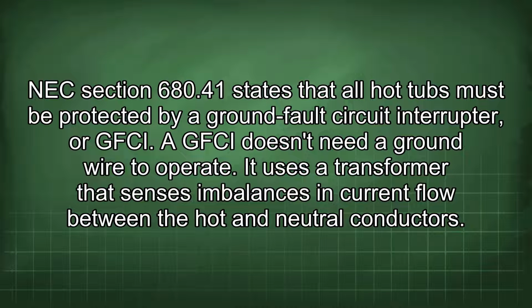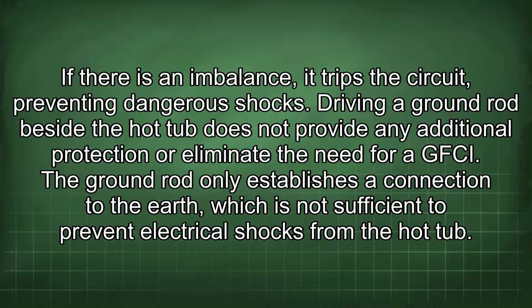NEC Section 680.41 states that all hot tubs must be protected by a ground fault circuit interrupter, or GFCI. A GFCI doesn't need a ground wire to operate. It uses a transformer that senses imbalances in current flow between the hot and neutral conductors. If there is an imbalance, it trips the circuit, preventing dangerous shocks.